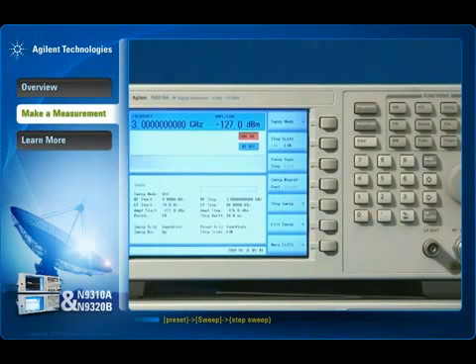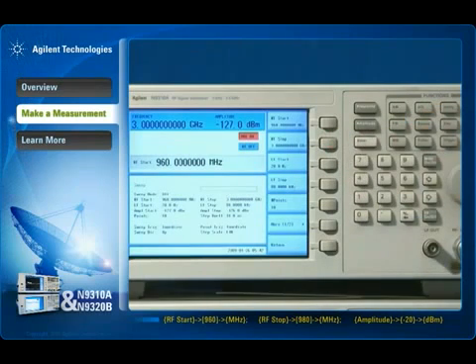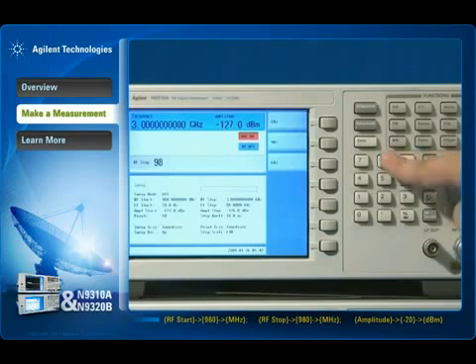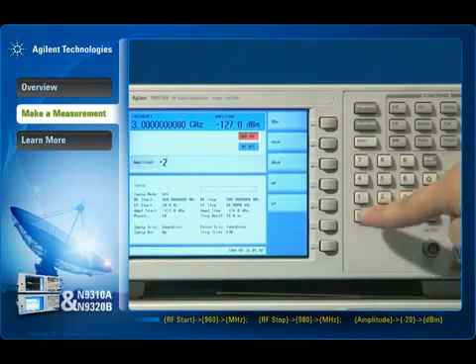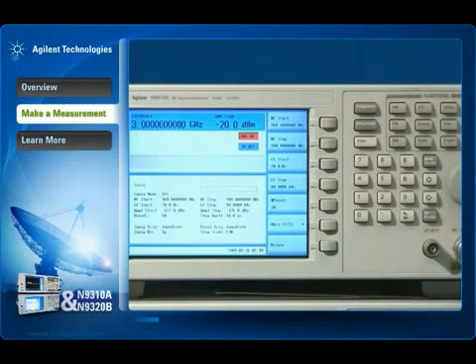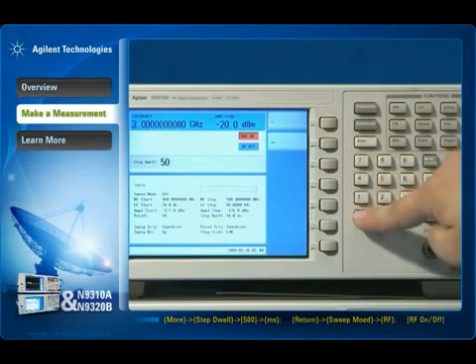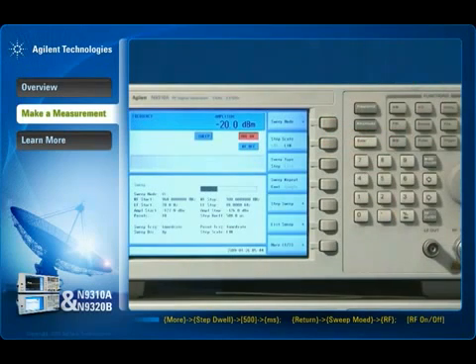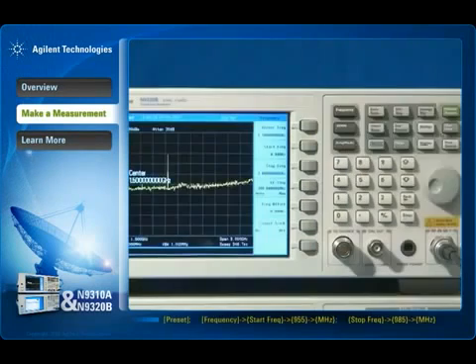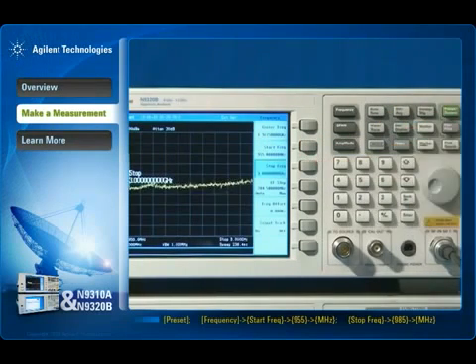First, enter the sweep submenu. Then set the start and stop frequency, and sweep output amplitude. Finally, set the dwell time at each point and activate the RF output. Now you have the 2 MHz step signals from 960 to 980 MHz with minus 20 dBm amplitude.